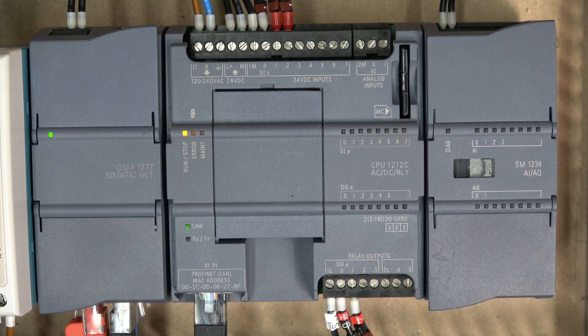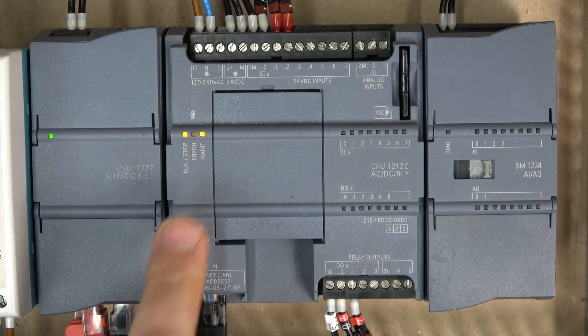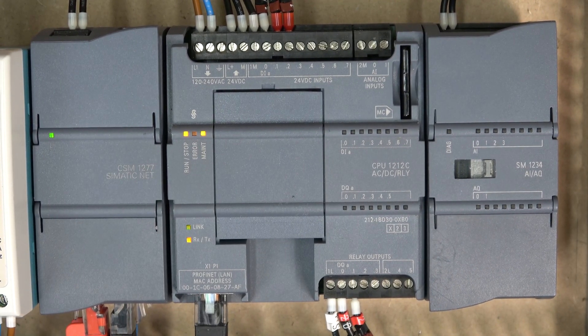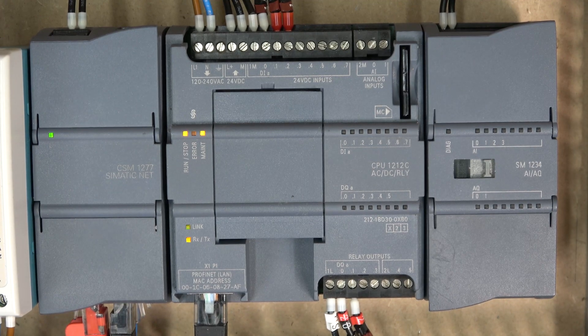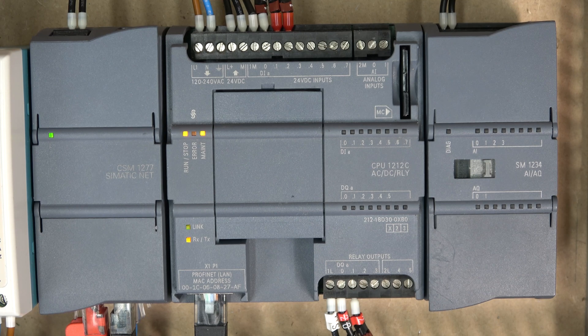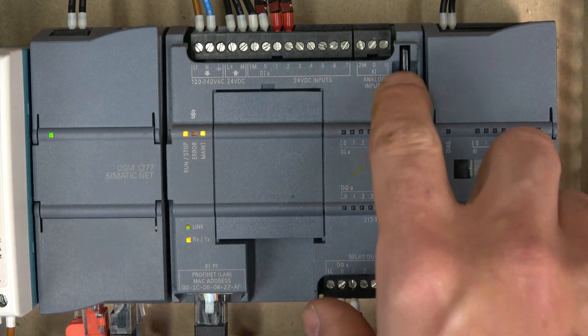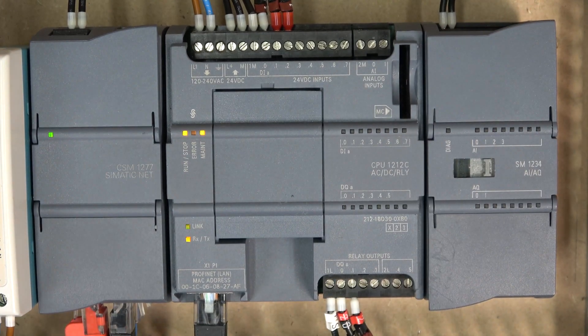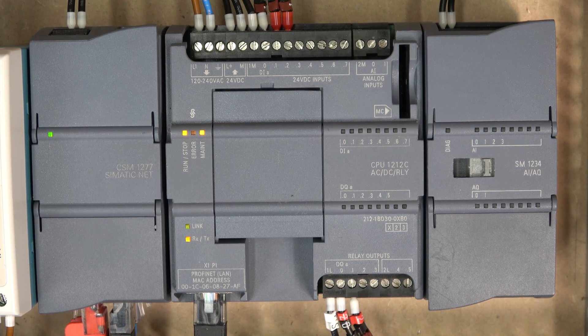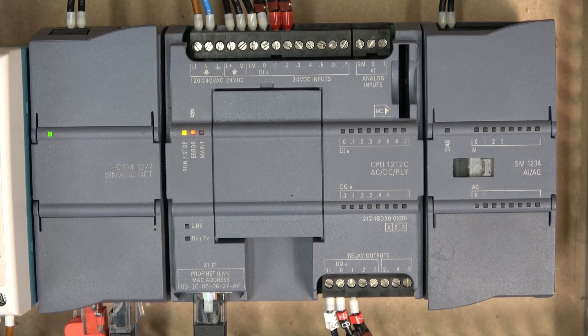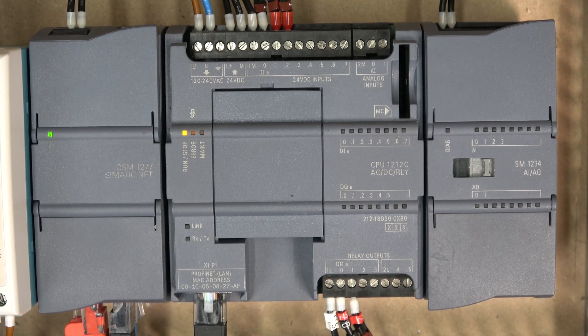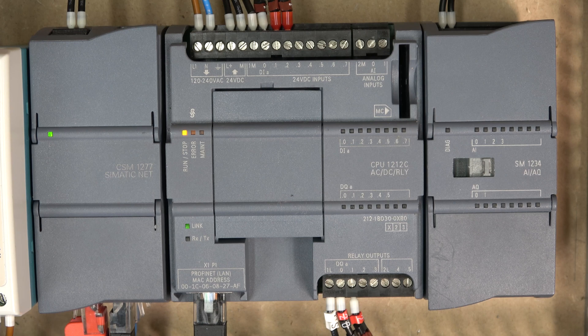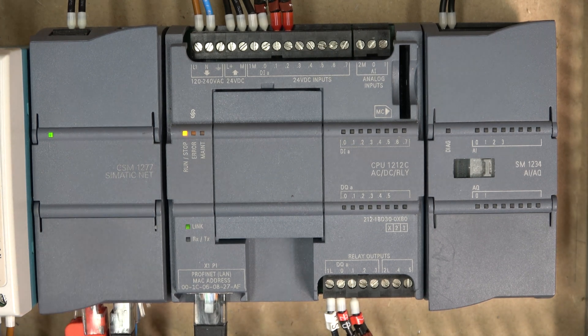Here we are. As you can see, run/stop has become a solid yellow and maintenance is flashing. That indicates the firmware update has been done and it's good to go. You need to remove your memory card now. We remove the memory card, then do one more power cycle - turn it off, turn it back on, and that should go into a solid yellow. There we go. Let's jump back on the computer and see where we are.